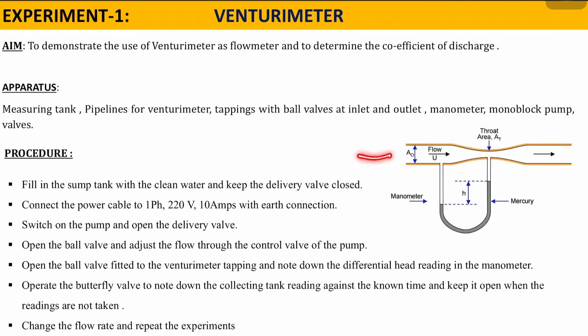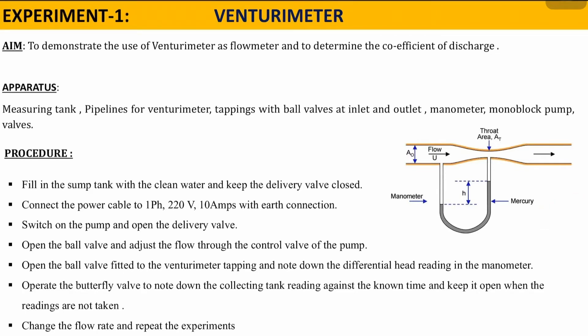This is the pictorial representation of the venturi meter. Water comes in at the inlet and exits at the outlet. This is the U-tube manometer. The venturi meter has two different diameters — the inlet area and the throat area — where the pipe contracts. Due to this contraction, a pressure difference is created, which is measured as head difference using the manometer. This is the basic concept of the venturi meter.